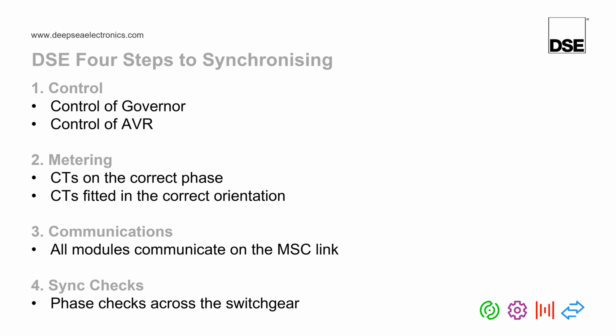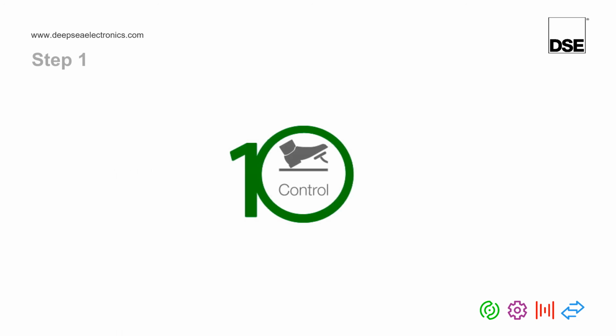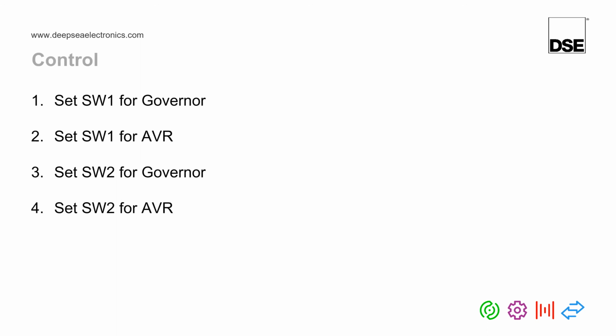So we'll carry on with the presentation. We're going to go through step 1 now, and step 1 is control. Each of the steps has its own mini steps within it, little procedures that we need to do. In terms of the control, we have 4 things to do: setting of switch 1 for the governor, setting of switch 1 for the AVR, setting of switch 2 for the governor, and setting of switch 2 for the AVR.